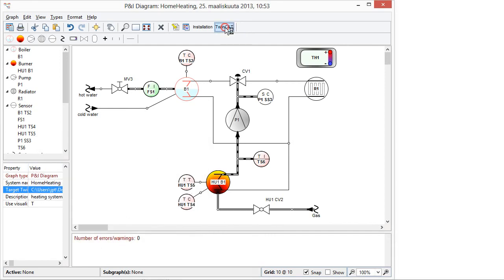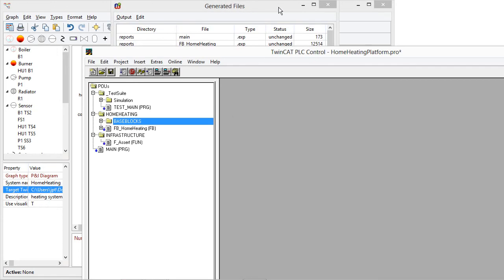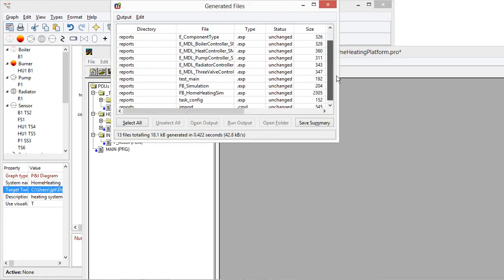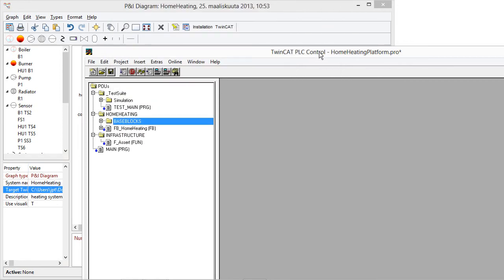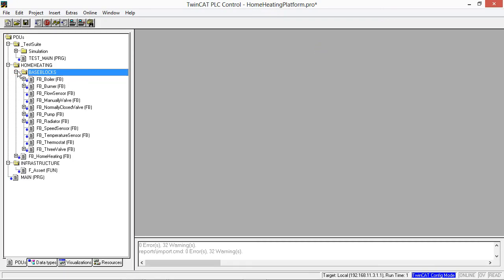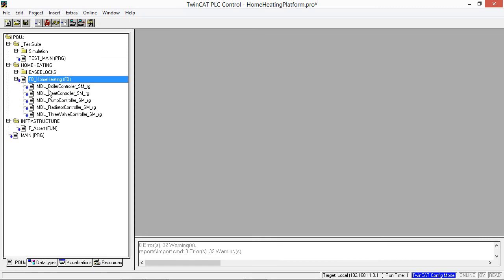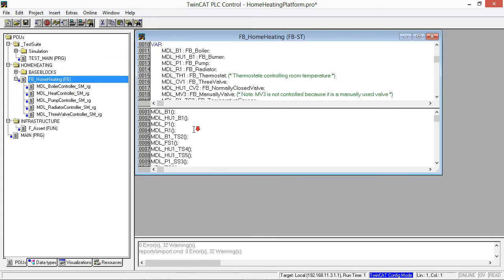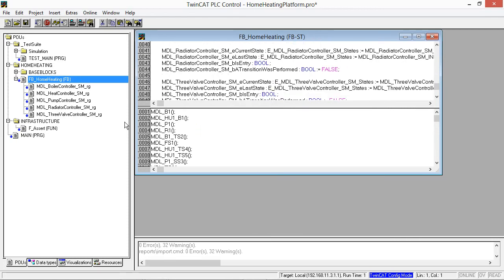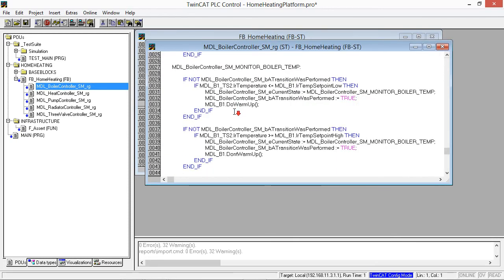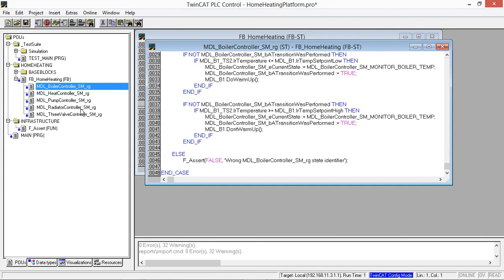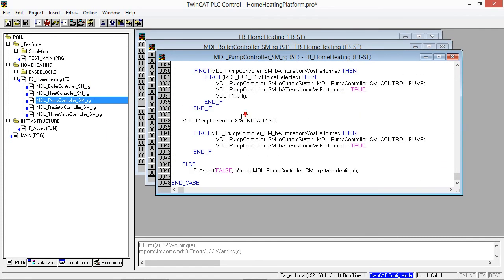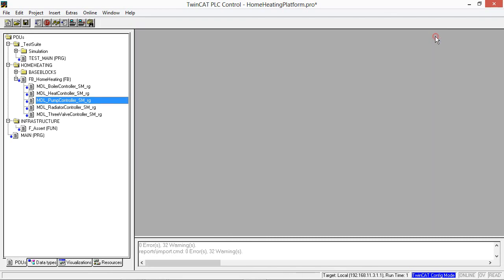Nothing to relate to our particular system like illustrated here. So the next what we would like to do is we would like to run this system. So I'm now generating the code, calling the TwinCAT PLC control. Here you can see the generated code. And now it's also included and imported here into this project, home heating platform project. So it has the base blocks but also have now the generated code from the models. So here you can see the different states and individual state machine implementations. Like for instance the pump over here. So this piece of code was generated from the model that you saw earlier for putting pump on and off.